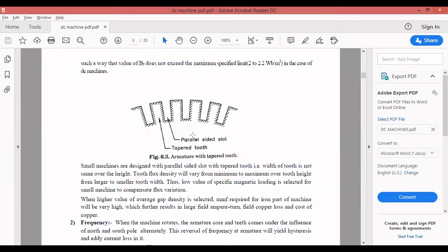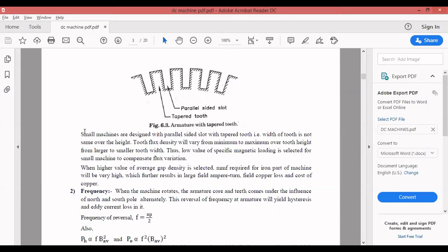If the armature rotates continuously, the frequency of reversal is given by f = n * P / 2, where n is in revolutions per second (n/60 in rps). Power loss due to hysteresis is proportional to f * B^1.6, and eddy current loss is proportional to f² * B². To keep total armature hysteresis and eddy current losses within the limit, a DC machine with a high frequency of reversal should not be designed for a large value of specific magnetic loading.